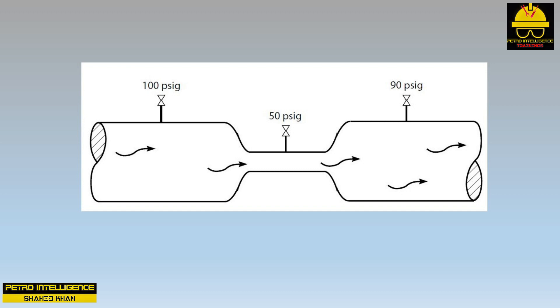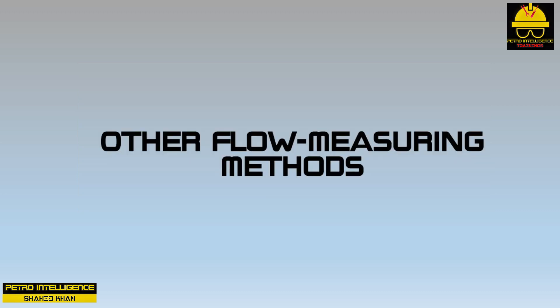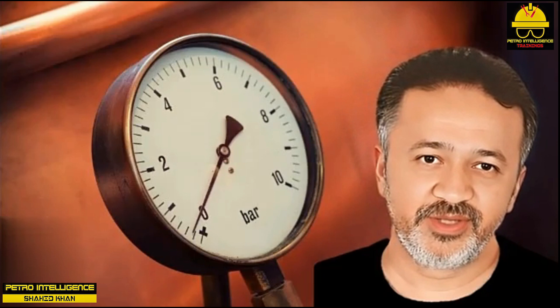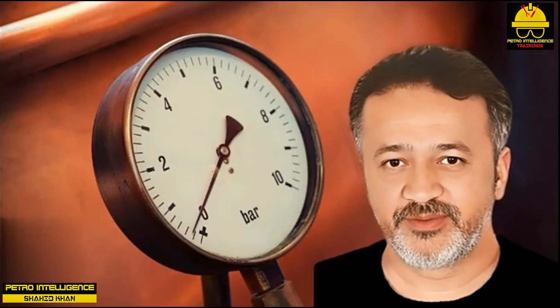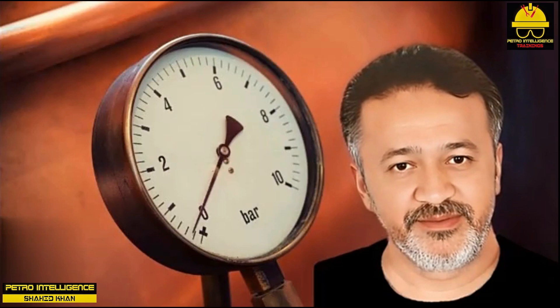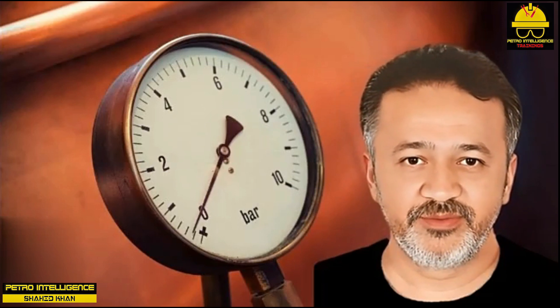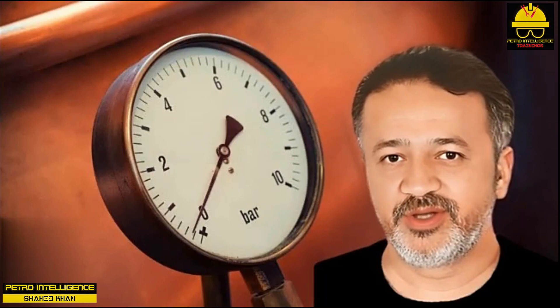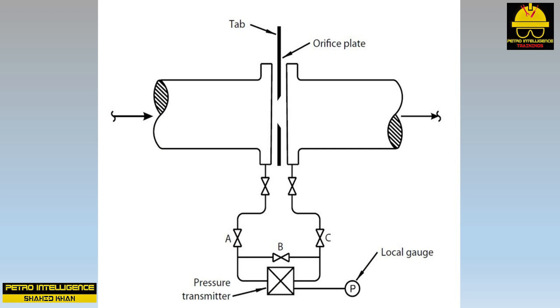Frictional losses represent an irreversible process, while conversion of pressure to velocity is reversible. Other flow measuring methods include vortex shedding meters, which induce vortex shedding across a tube and measure vortex velocity — with no orifice taps to plug. Doppler meters measure fluid velocity based on how the speed of sound is affected by flow. Rotameters measure how far a ball or float is lifted in a vertical tube. However, the vast majority of flows in most process plants are still measured with orifice plate flow meters.